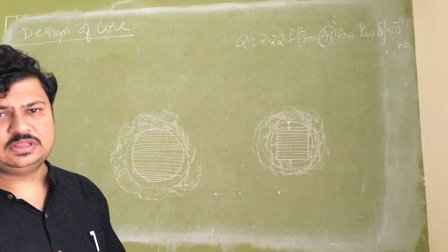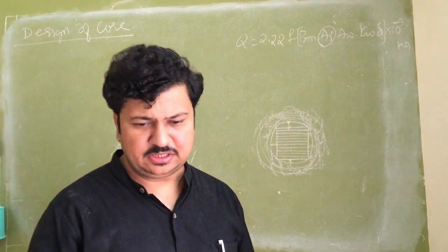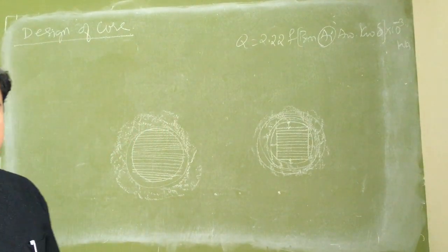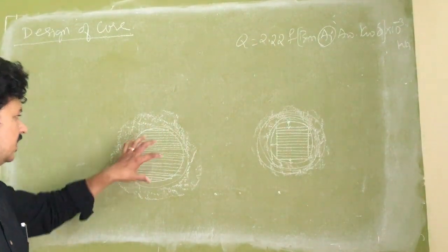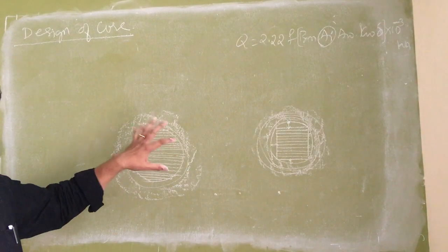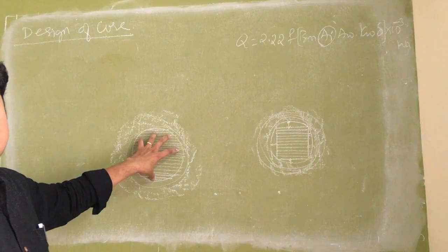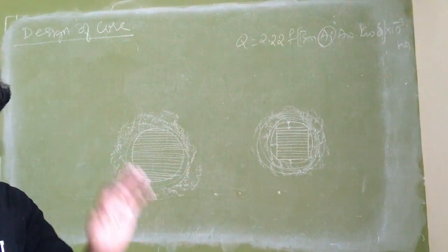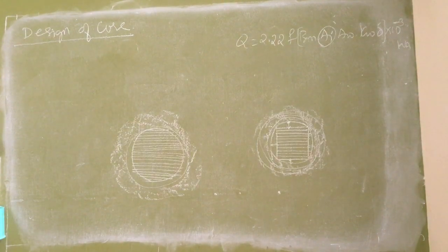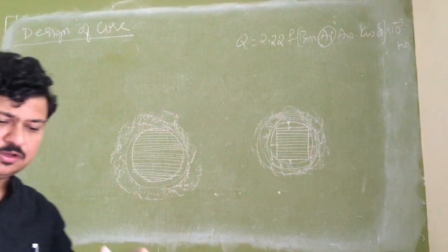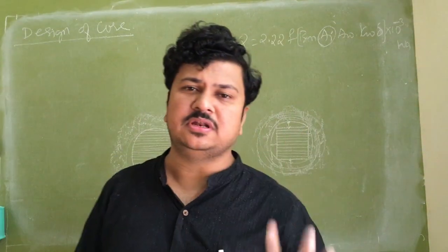the core, whether it is rectangle, whether it is square, whether it is stepped, to the circular cross section area, and I will obtain a relation with respect to the circular cross section area, because circular cross section is the maximum utilization area of the circumcircle. So what I am finding here is how much area of the core is utilized in a circumcircle.